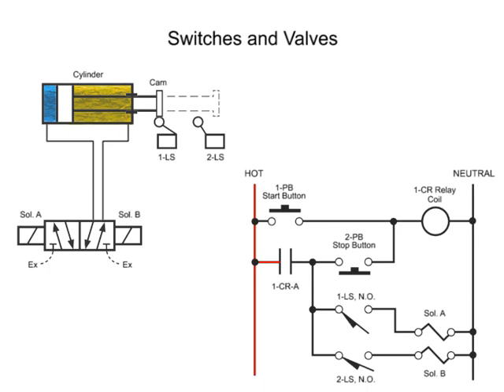With both solenoids de-energized, the hydraulic valve remains in its current position and the cylinder will continue to travel in its current direction until it reaches the end of its stroke.